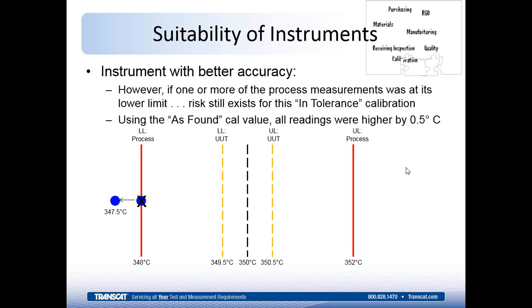Now, the instrument itself was found in tolerance, and it wouldn't trigger a flag for you to go back and look at that. But you understand there are some process measurements that could be bad, and you'd have to go back and look at all of them to determine which ones it affected. That could be cumbersome and costly. So how do you build something in to prevent that without having to go back and look at everything?